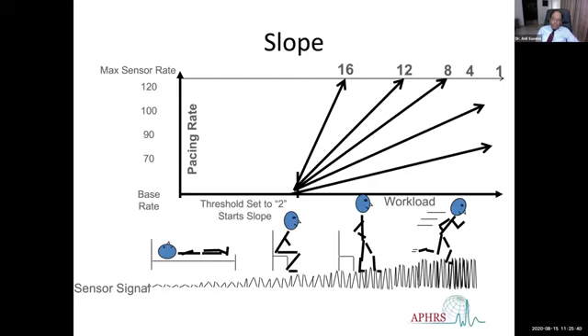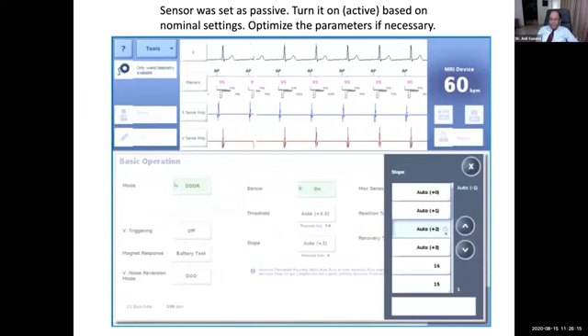This is the patient who came with a flat heart rate of 60, and we can go to the parameter settings. Then we go to the sensor. It was in passive mode. We can switch it on, and we can program the maximum sensor rate. We can check the threshold as we want. We can program the slope, so the programming is done, and the patient's problem will be solved.